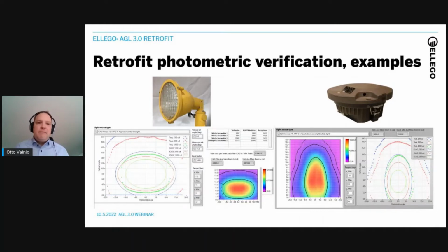But if we put an LED bulb into an existing halogen fixture, we try to match the luminous output of the halogen as well as we can with the LED, but it's not exactly the same. The luminous output from an LED is so much different from a halogen that it actually takes a little bit of effort to make it look like a halogen. I think we've done pretty good work with that, but we think that it's crucial to photometrically test each new fixture type we encounter.